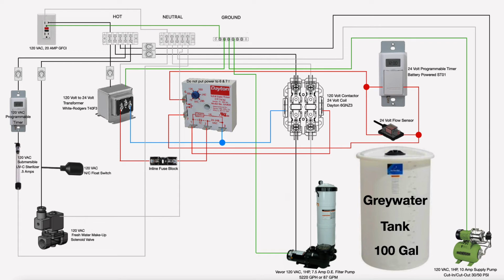Last thing I want to note, the 24-volt battery-powered timer and the 24-volt flow sensor each have power flowing to one side of them at all times from terminals 6 and 7 on the time delay relay. When the timer closes its internal switch, meaning it's ready to run the program that you set it to run the filter pump on, so let's say you run the filter pump 2 hours in the morning, 2 hours at night, or when the flow sensor senses water flowing over its contacts, that will close and complete the circuit back to the relay across terminals 6 and 7 on that time delay relay, which again, either one of those will then cause 24 volts to be sent over to the coil on that contactor to energize the filter pump.